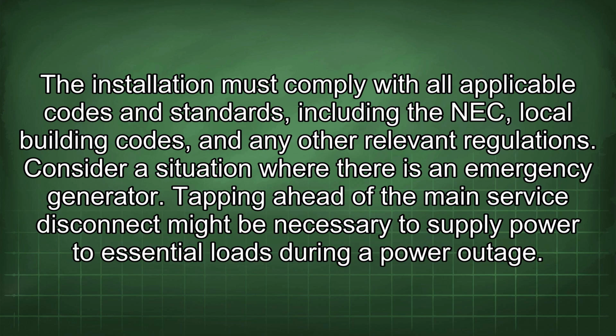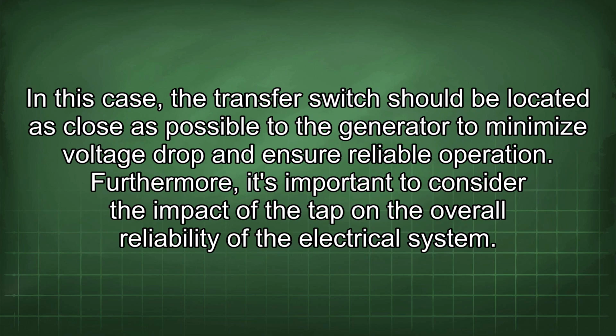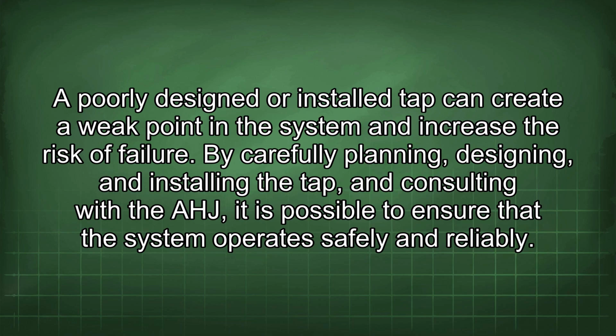Tapping ahead of the main service disconnect might be necessary to supply power to essential loads during a power outage. In this case, the transfer switch should be located as close as possible to the generator to minimize voltage drop and ensure reliable operation. Furthermore, it's important to consider the impact of the tap on the overall reliability of the electrical system. A poorly designed or installed tap can create a weak point in the system and increase the risk of failure. By carefully planning, designing, and installing the tap, and consulting with the AHJ, it is possible to ensure that the system operates safely and reliably.